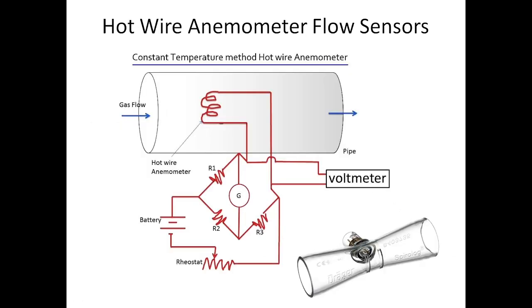Hot wire anemometer flow sensors. This is a style that's used by Dräger pretty commonly. It requires a heating element, which you can see right here on these two prongs. It heats up, and as gas flows by that heating element, the faster the gas, the more that heating element cools off. Now this type of flow sensor does particularly well when it comes to moisture because you're heating something up, so obviously water isn't going to want to condensate in that region. However, this little tiny filament is kind of like a light bulb filament, and it can and will eventually break. It has a life expectancy.